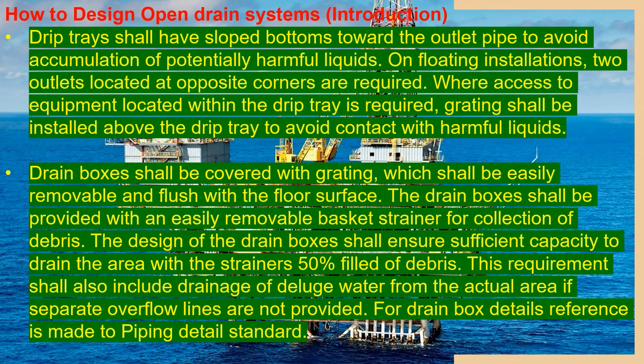The drip tray shall have sloped bottoms toward the outlet pipe to avoid accumulation of potentially harmful liquids. On floating installations, two outlets located at opposite corners are required.